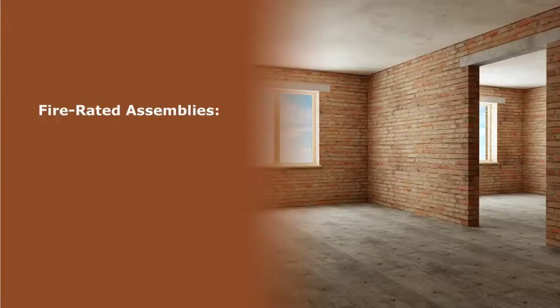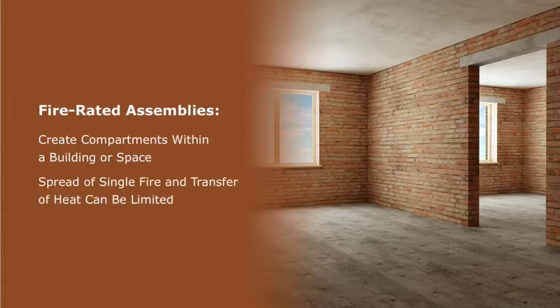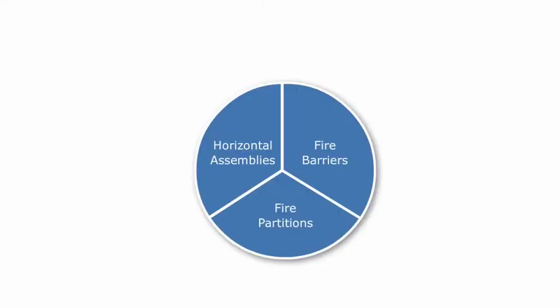Fire rated assemblies are used by the codes to create compartments within a building or space by separating different areas, sometimes both horizontally and vertically, to limit the spread of a single fire and transfer of heat. There are three basic types of rated assemblies: fire barriers, fire partitions, and horizontal assemblies. The codes determine when each type is required to provide the appropriate level of compartmentation.